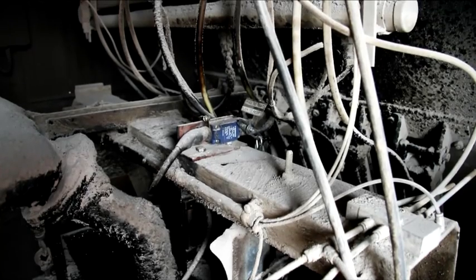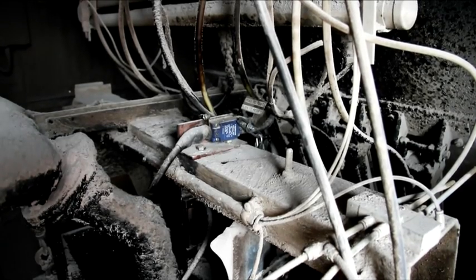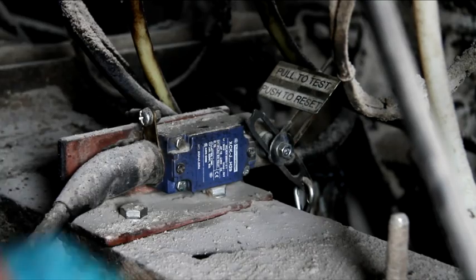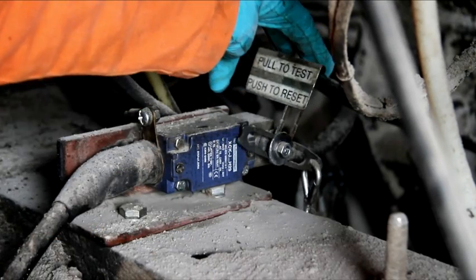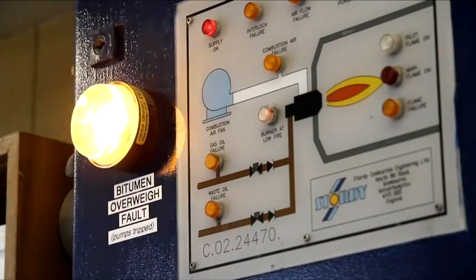Once the float has been set up, there is no further calibrations required and the system can be easily tested at any time of the day by any operative by just simply pulling back the limit switch and checking the pump drops out.